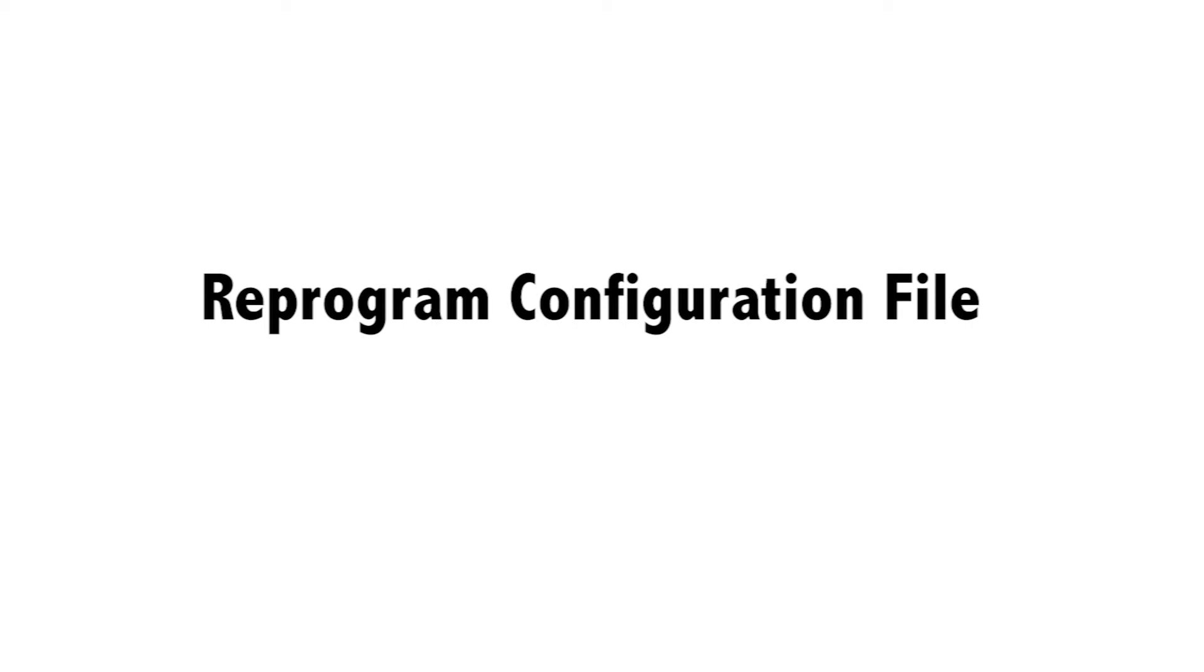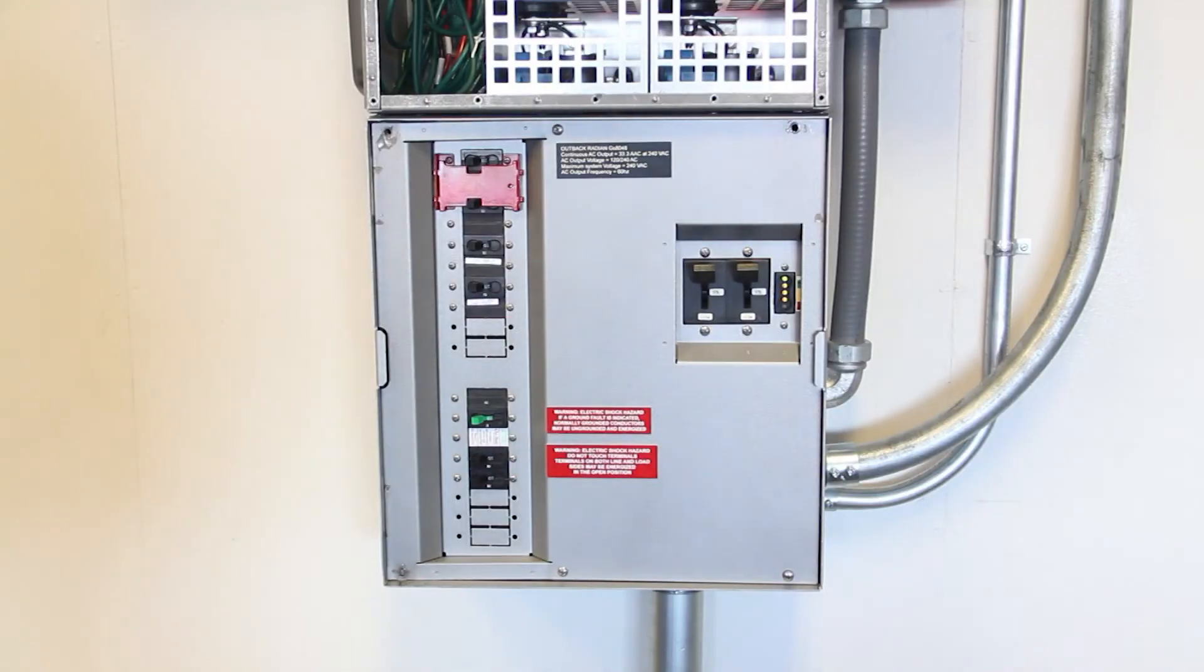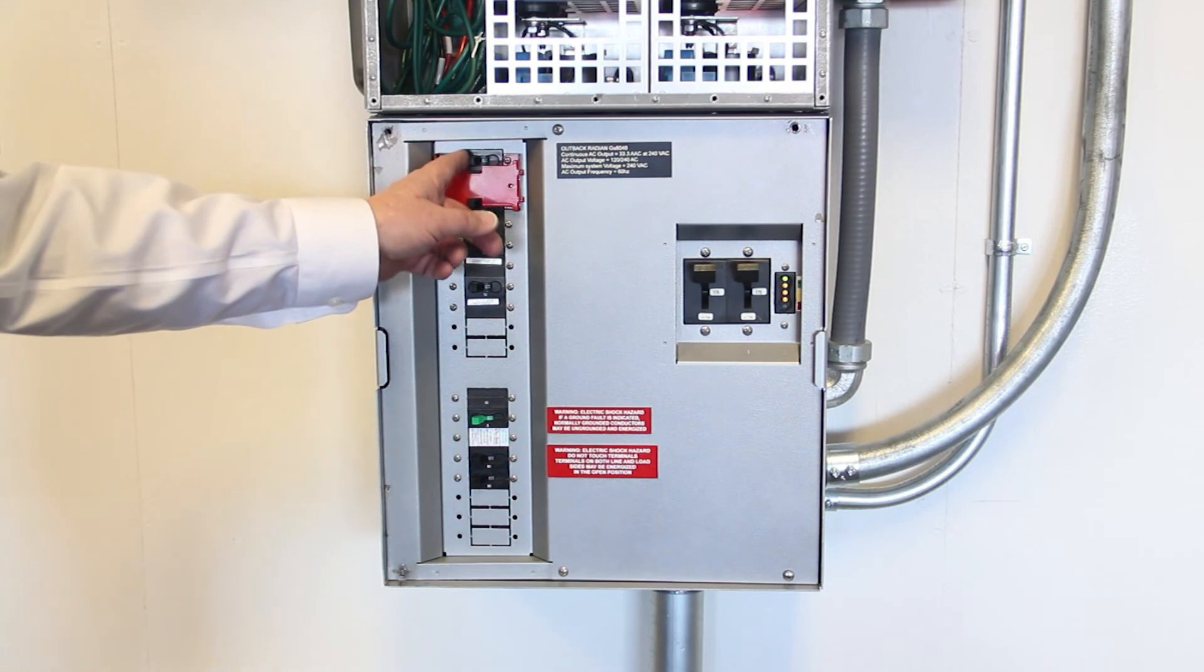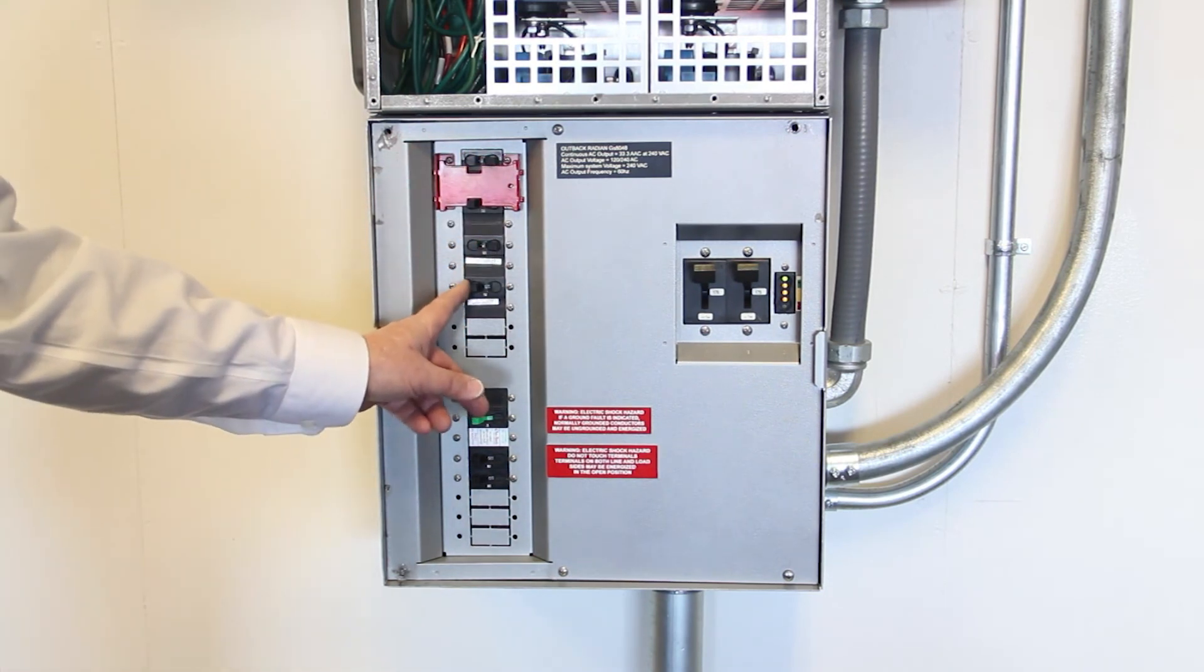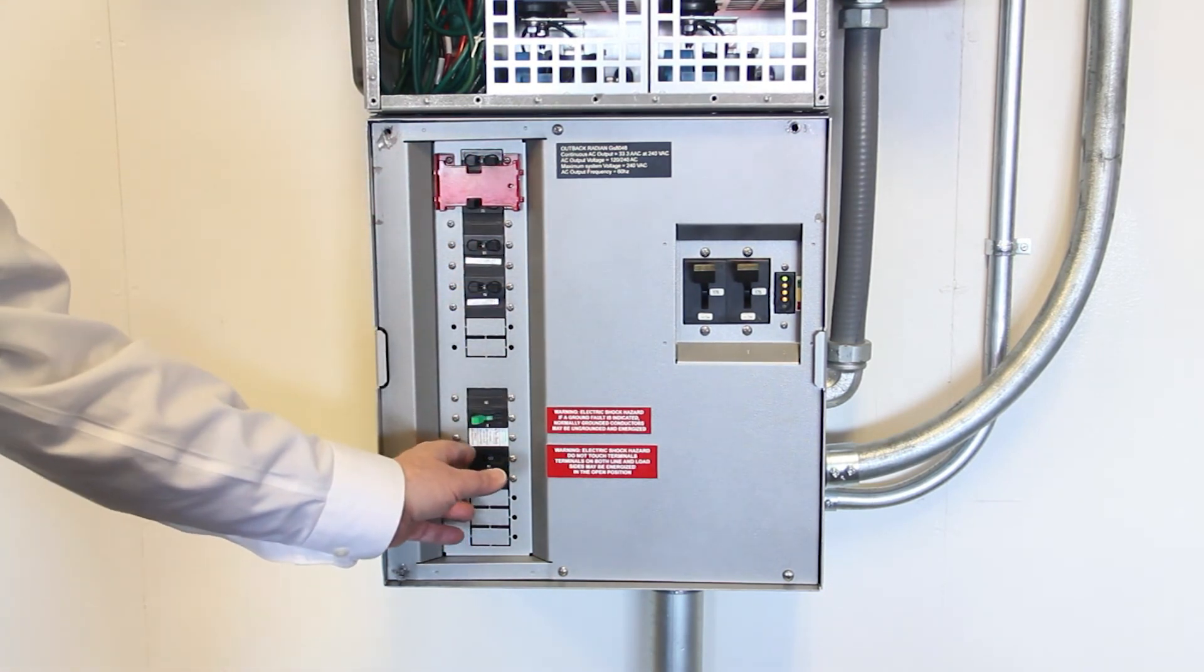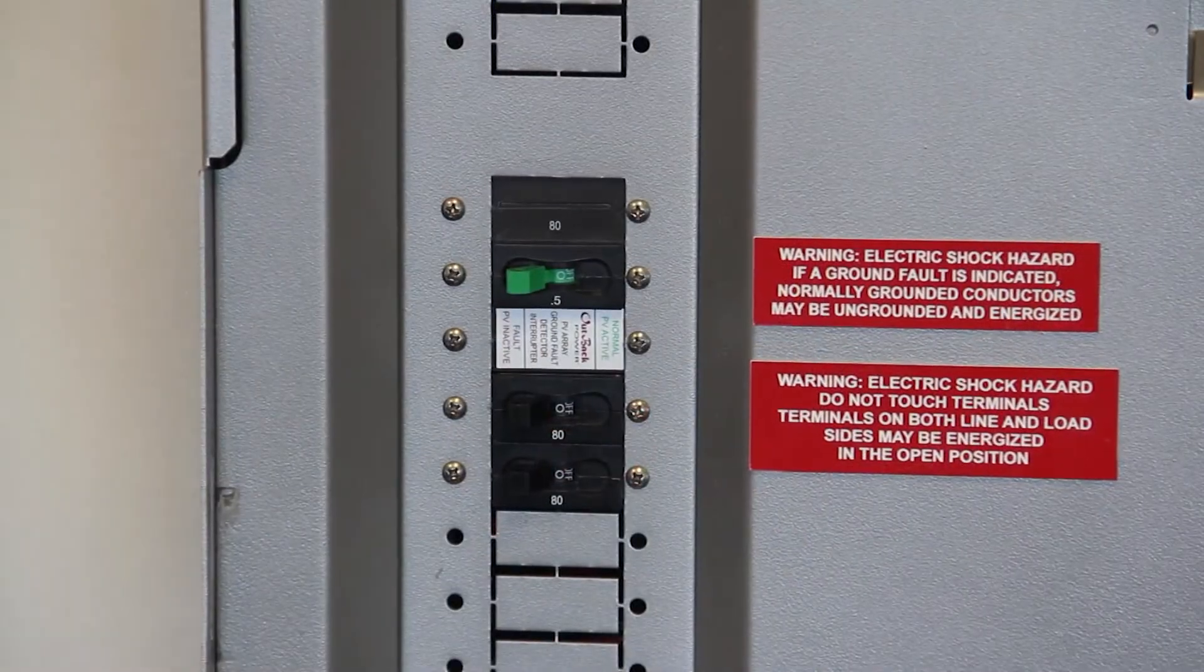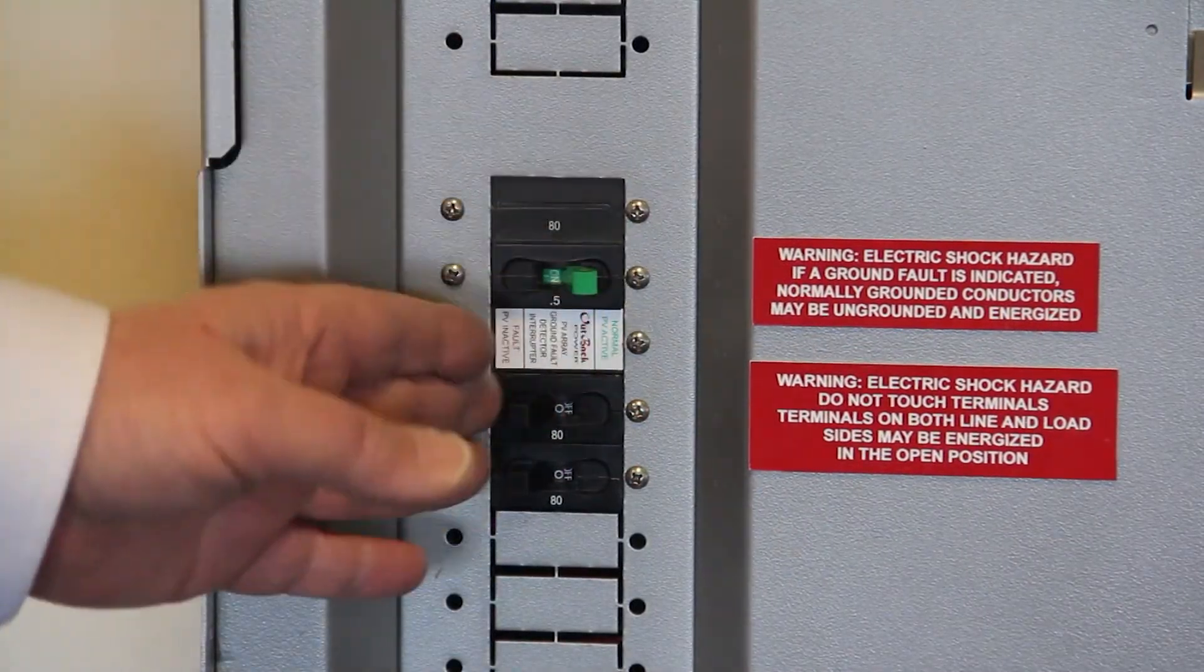Using the Mate 3, reprogram the configuration file previously saved, or make the necessary changes per your application. Note, Radian's GS3548E and GS4048A must be reprogrammed for their specific model by entering the installer password and changing the model select. Turn on the AC output breaker. Turn on the grid input breaker. Turn on the generator input breaker. Turn on the charge controller breaker or the GFDI. Turn on the PV input breaker.